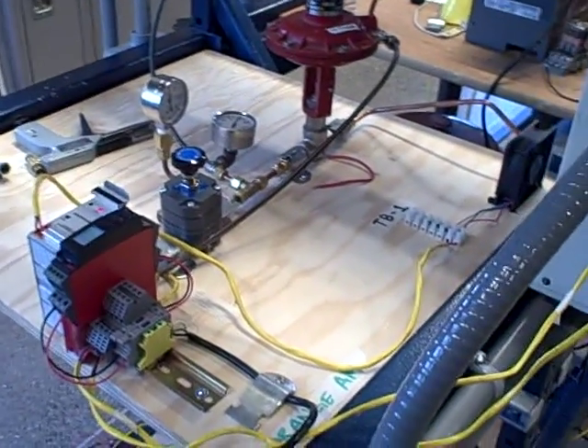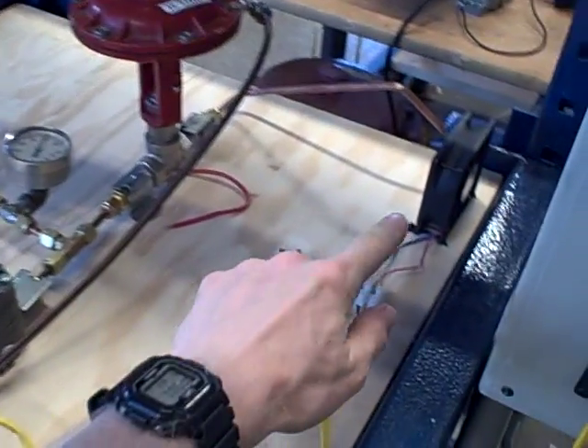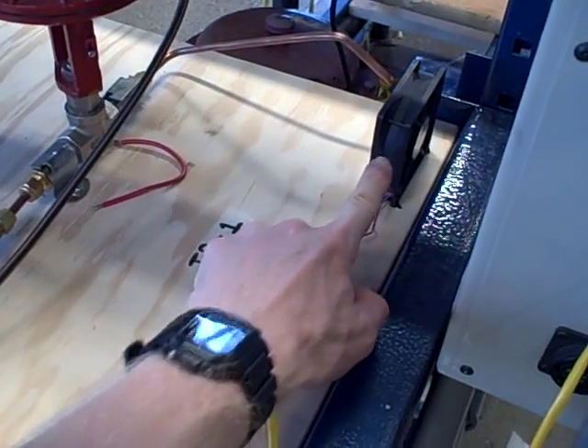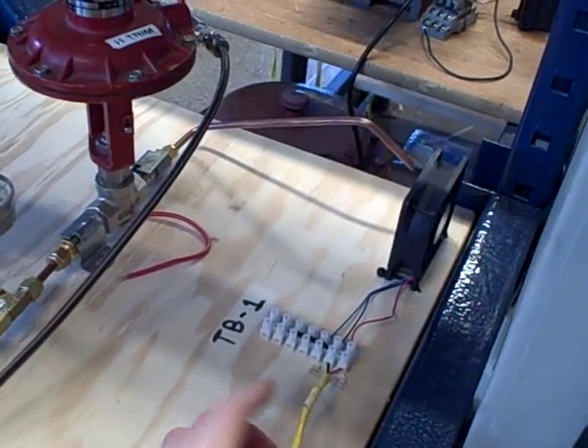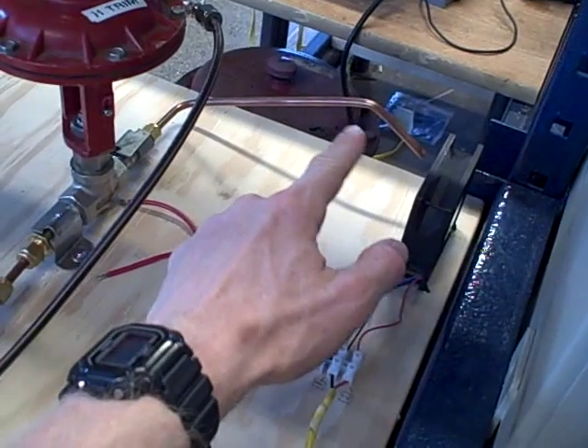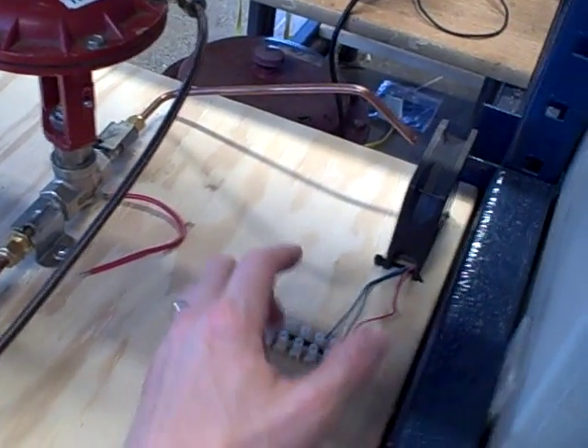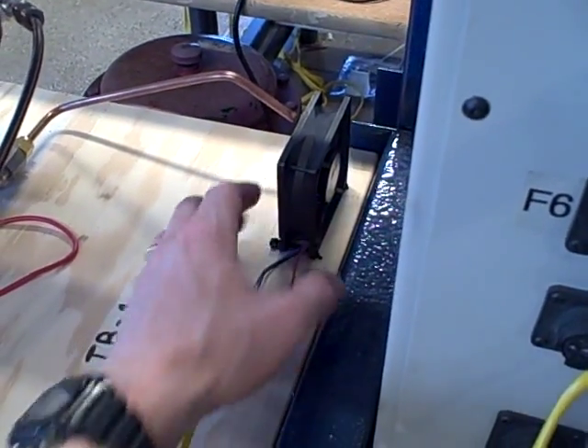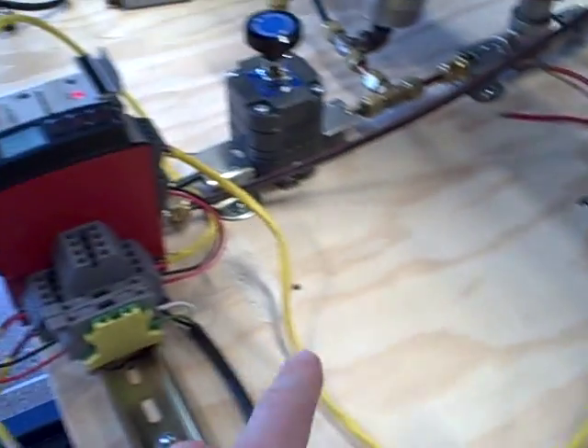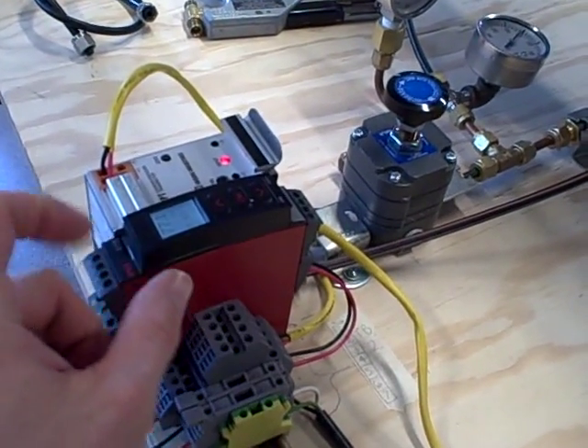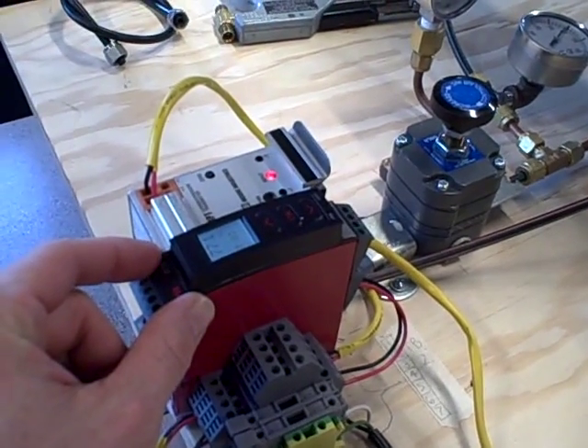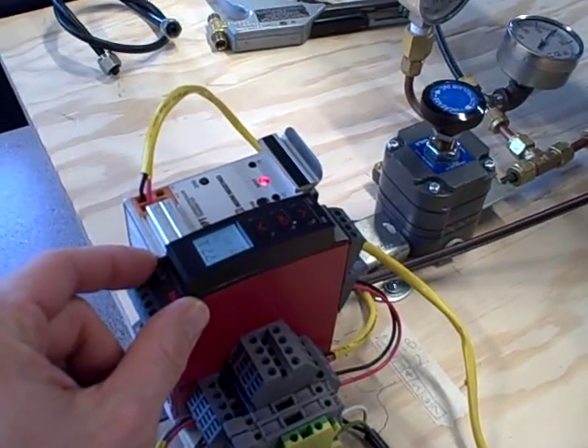Here we have a small demonstration process consisting of a muffin-style DC air fan that's acting as a turbo generator. We blow air at it, compressed air, through a copper tube nozzle that spins the blades of the fan, generating a DC voltage. That DC voltage is interpreted by this transmitter device, converting it to a 4 to 20 milliamp signal that represents the fan speed.